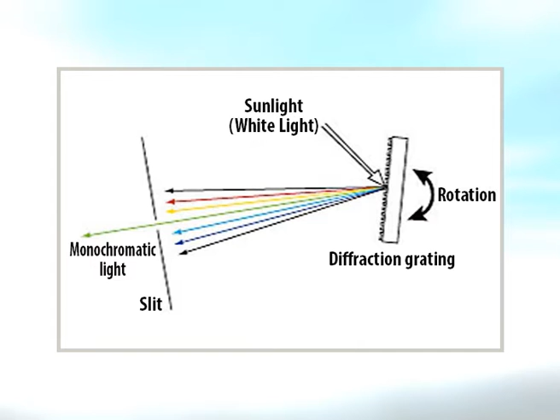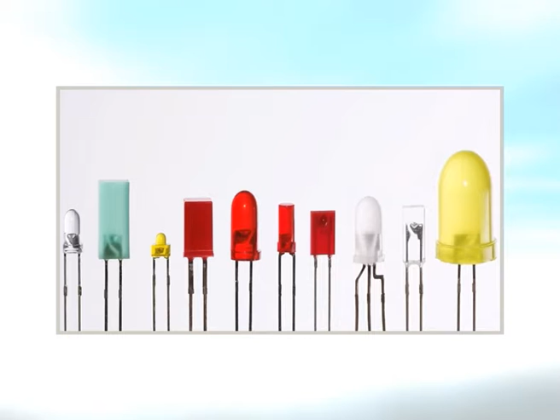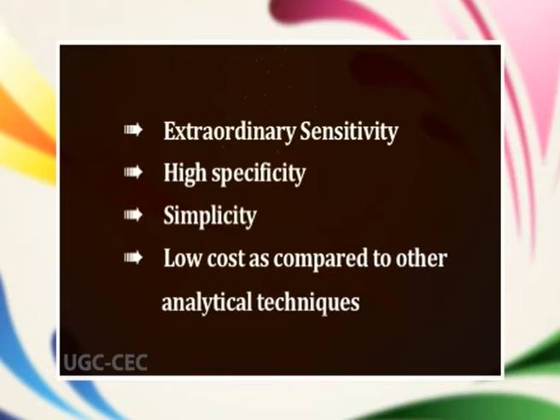Fluorometers employ monochromators, that is, a spectrofluorometer, optical filters, that is, a filter fluorometer, or narrow band light sources like LEDs or lasers to select excitation and emission wavelengths. Fluorometry is chosen for its extraordinary sensitivity, high specificity, simplicity, and low cost as compared to other analytical techniques. Fluorometry is ordinarily 1000-fold more sensitive than absorbance measurements.